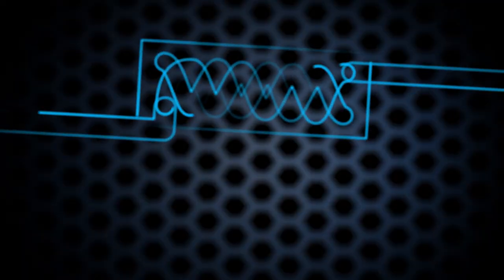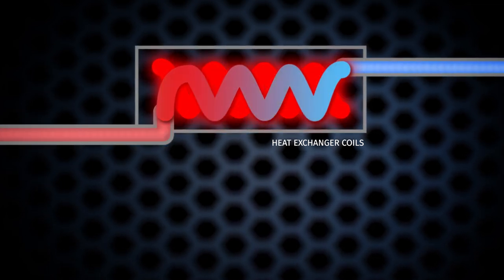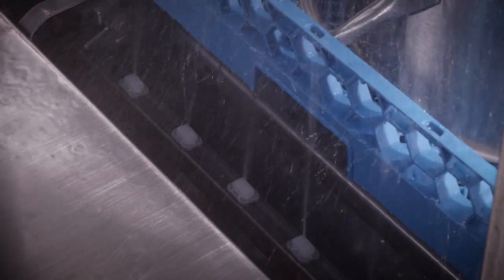The heat that is captured in the heat exchanger preheats the incoming cold water to 110 degrees or more. The preheated water then travels to the booster, where a final rinse temperature of over 180 degrees is reached.